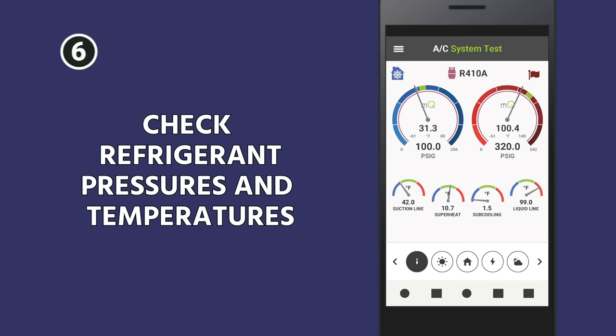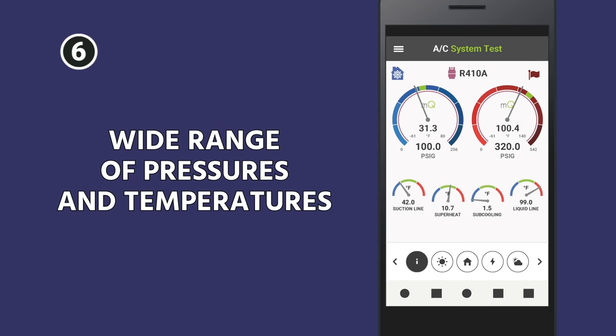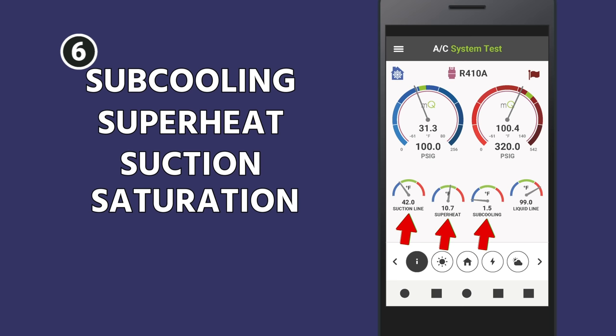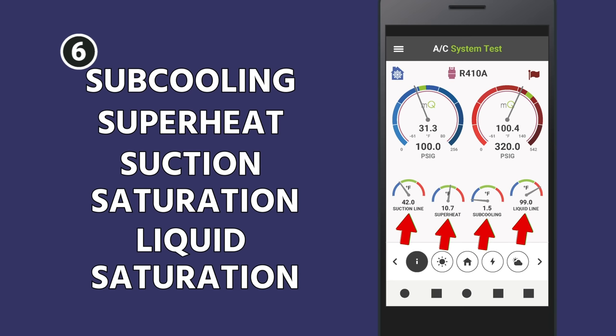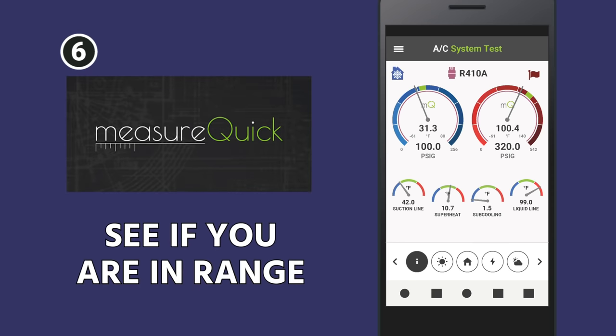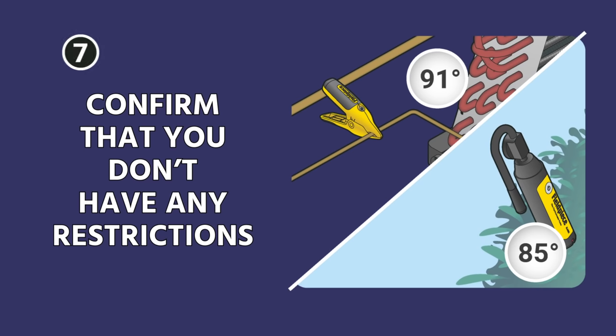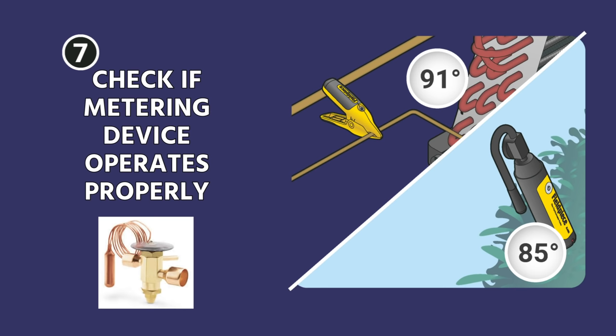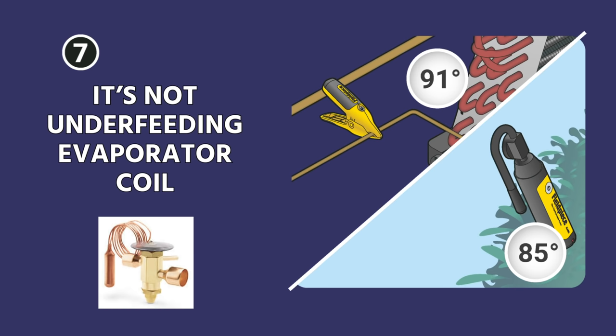Once you're done with that, you want to check your refrigerant pressures and temperatures. Check your subcooling, your superheat, your suction saturation, your liquid saturation. A really good tip is to use the MeasureQuick app to make it easy and see if you are in range. You want to confirm that you don't have any restrictions — things like a temperature drop across a liquid line filter dryer. You also want to check and make sure that your metering device is operating properly and that it's not underfeeding the evaporator coil.